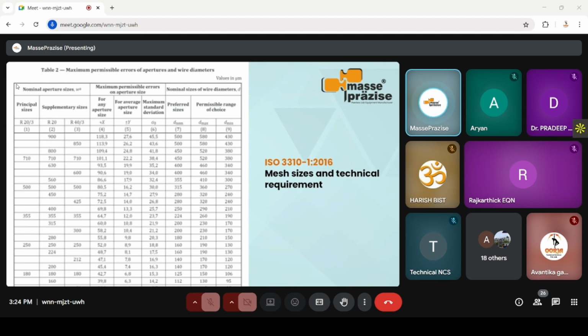So if we are taking 100 observations, the average variation should be within the plus or minus range of 22.2 micron, and the average of the maximum standard deviation can be 38.4 micron for these 100 or 150 or 200 observations, whatever we are taking. So if all the data is within this range, then that means the mesh is as per the standard requirement of ISO 3310.